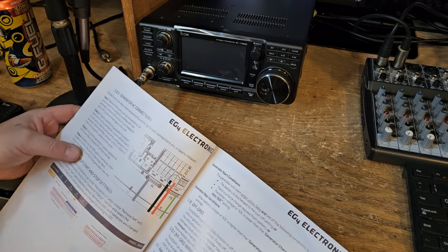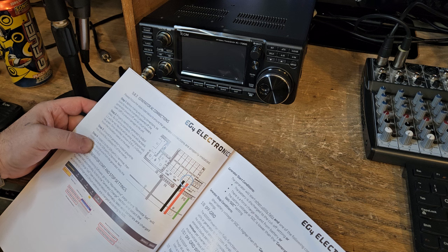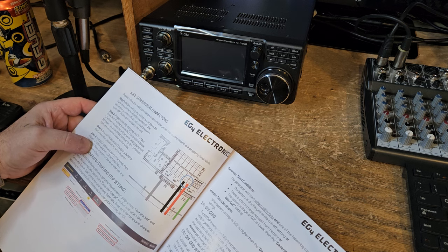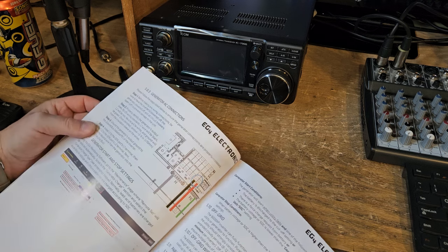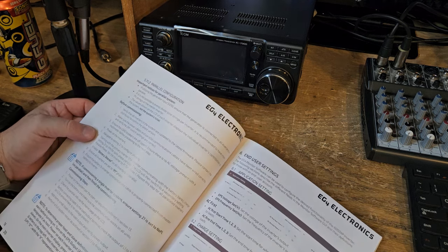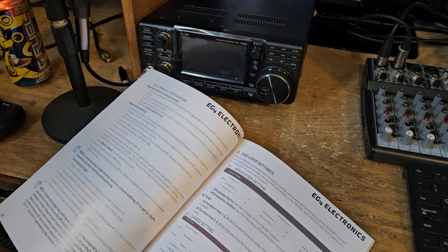Off-grid wiring. The XP can accept 50 amps, 12 kilowatts of generator power and will pass through all available power to the loads. Therefore, the load's subpanel can be sized up to the size of the backup generator with 50 amps minimum per inverter. Parallel wiring information, I'm not going to get into all that.